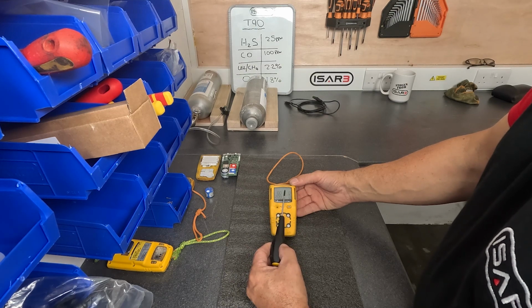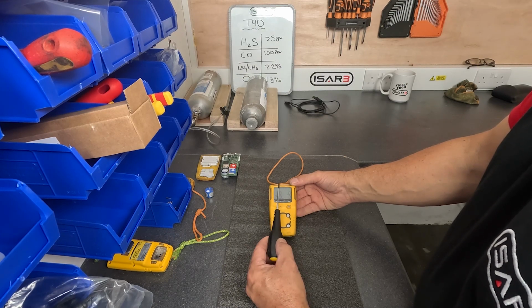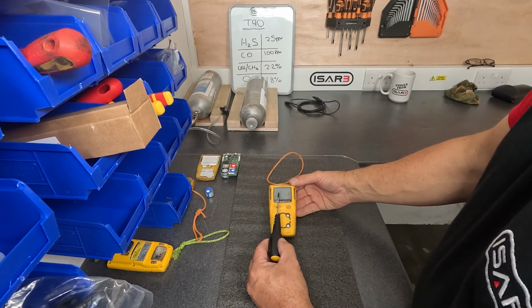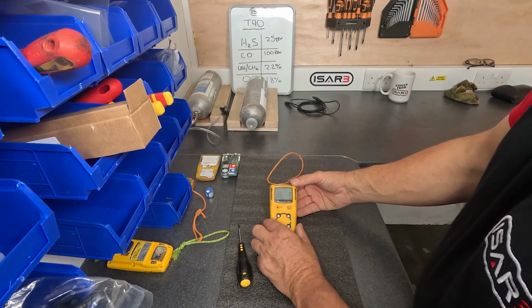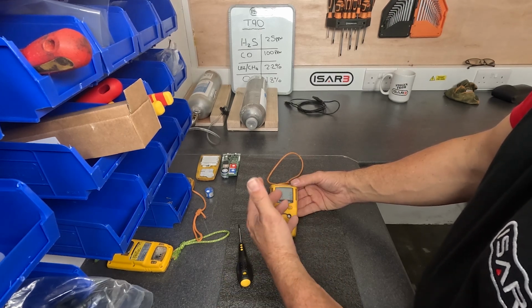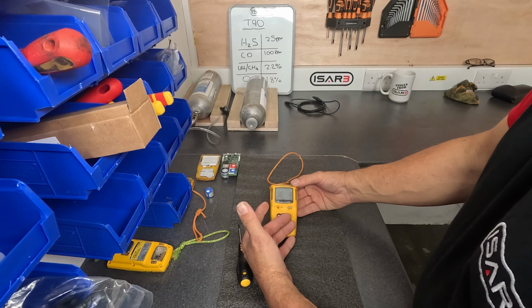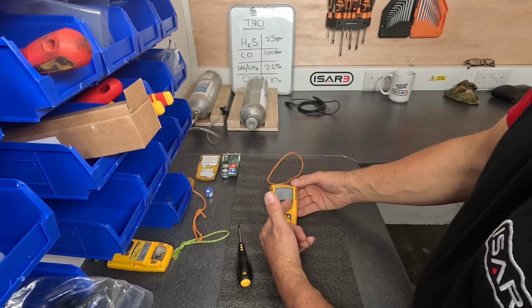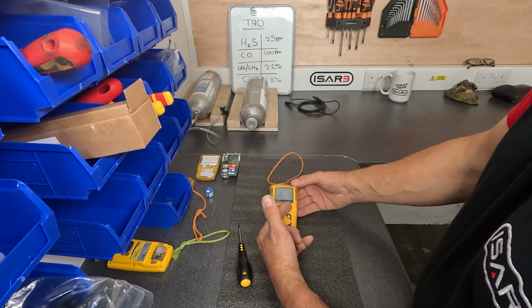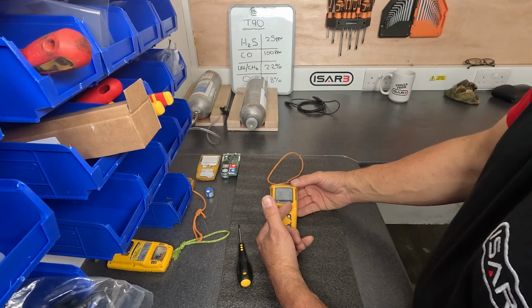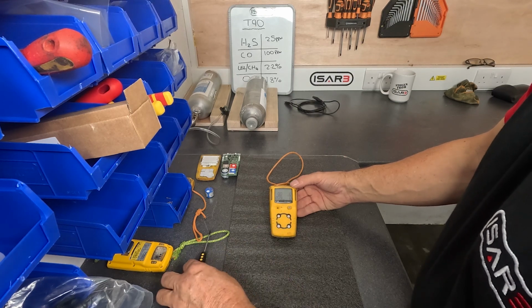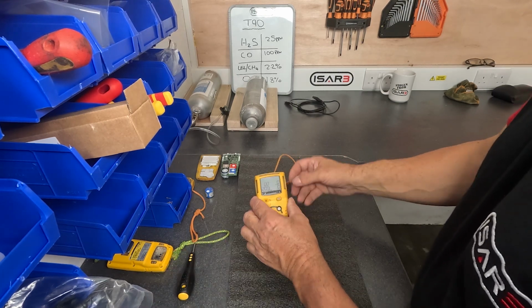And then the other three sensors on here, so your flam sensor, your carbon monoxide, and your H2S sensor on this particular gas detector. Your test, the gas detector will test that the circuit's working, but it won't tell you how accurate these sensors are. So the only way you can do that is with a bump test. And so you should be taking students through how to do the bump test.